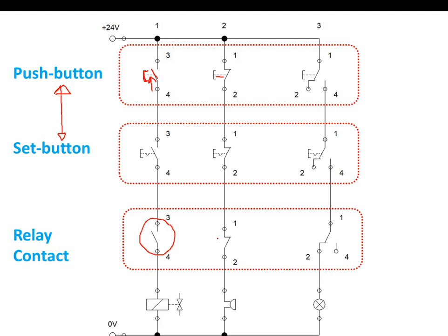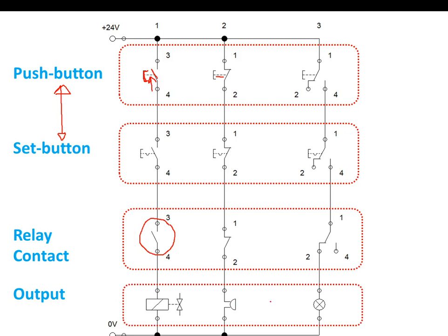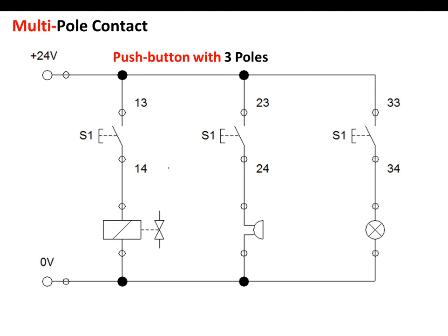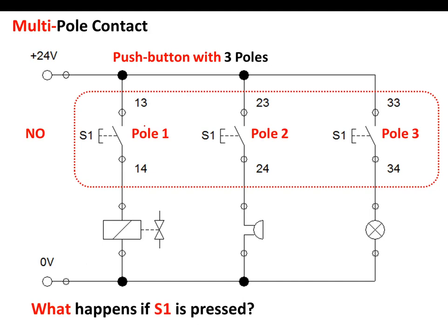The outputs include solenoid, buzzer, and lamp. With regard to poles and contacts, a pole refers to the first figure in the numbering system — one refers to pole one, two to pole two, three to pole three. The second number is the contact number: 3-4 means normally open. The benefit of multiple contacts is that once the push button is pressed, all poles are simultaneously activated.